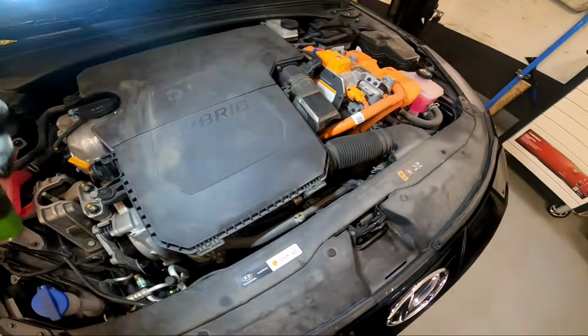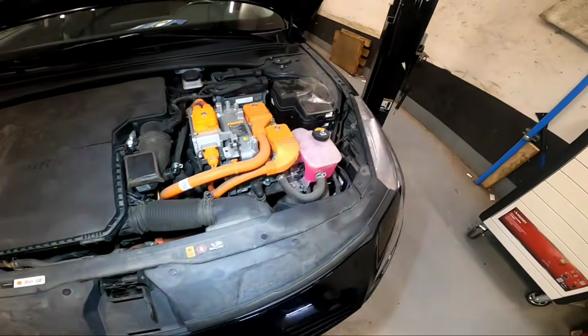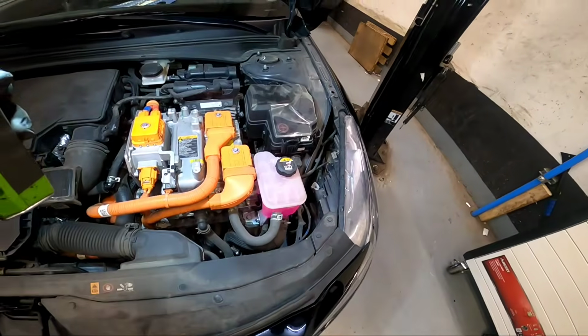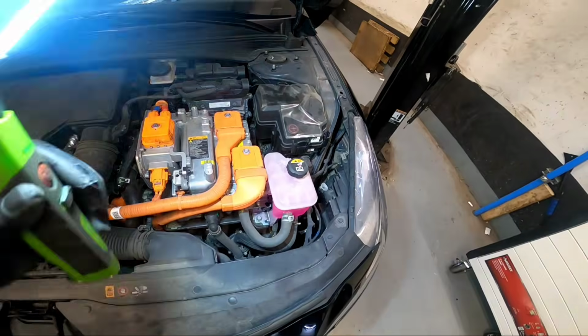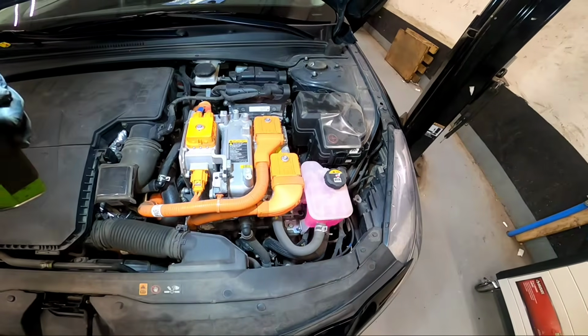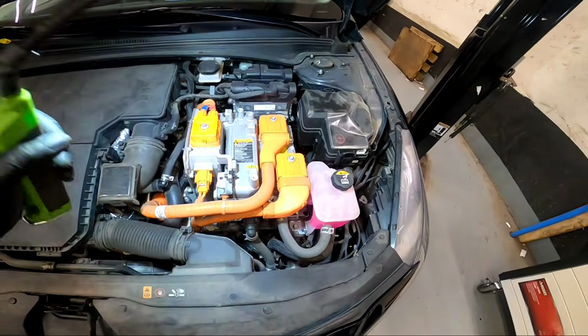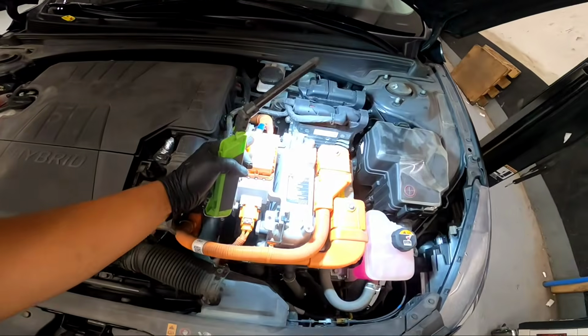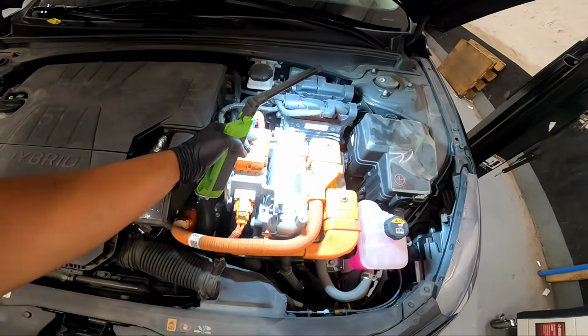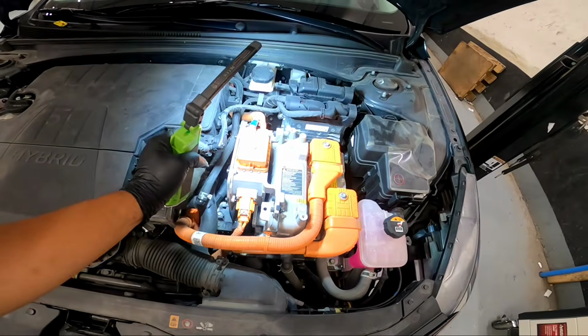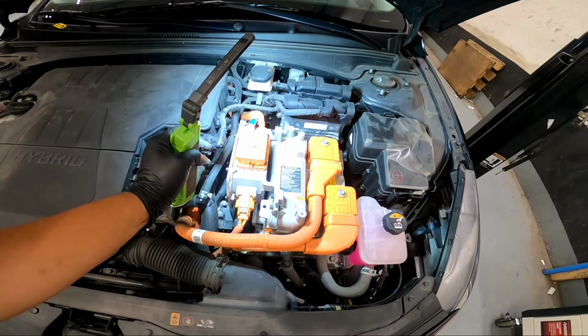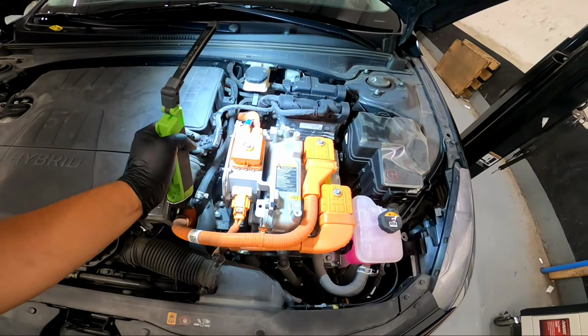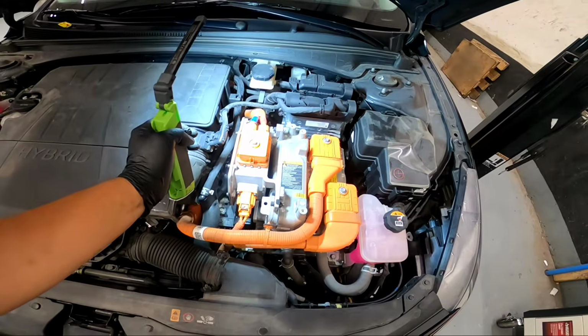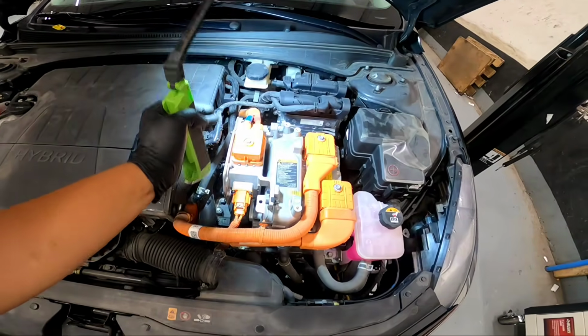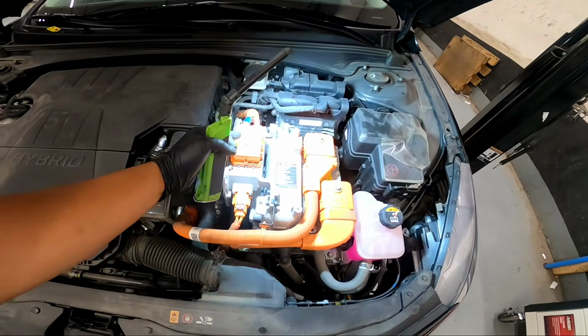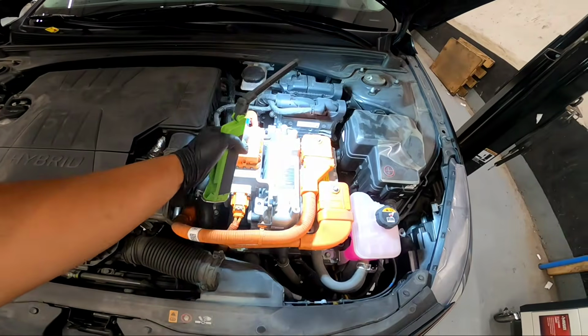So you wait 5 to 10 minutes before you start taking apart the high voltage system, right? Let's remove this, because this is coming from our battery system. We remove this, measure our voltage first, and make sure that we're safe, that it's below 30 volts as per the shop manual. And we're good to go. So I'm going to wait 5 to 10 minutes and then remove this connector here.